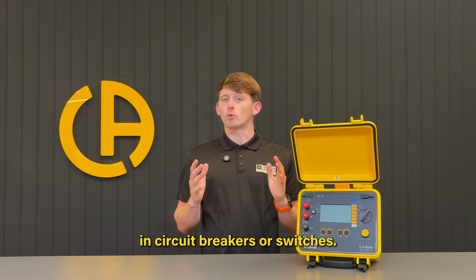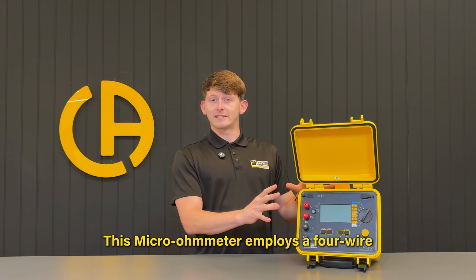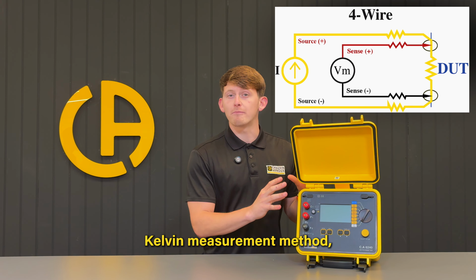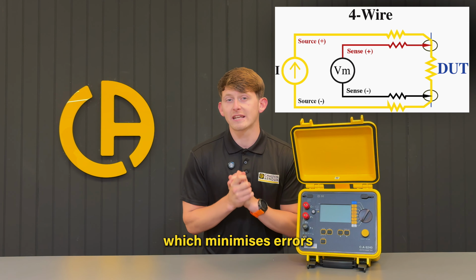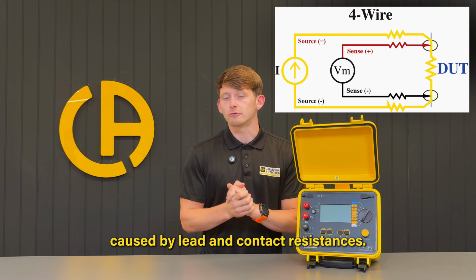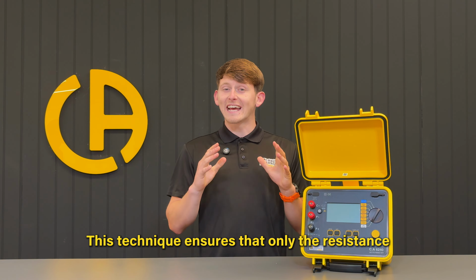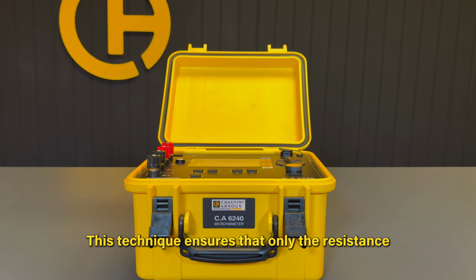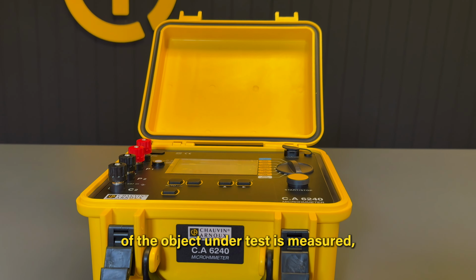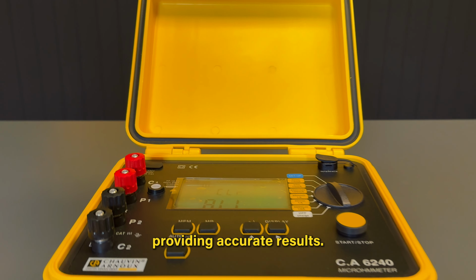circuit breakers or switches. This micro-ohmmeter employs a 4-wire Kelvin measurement method, which minimises errors caused by lead and contact resistances. This technique ensures that only the resistance of the object under test is measured, providing accurate results.